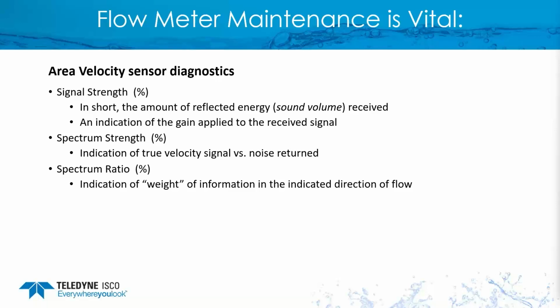Now the spectrum ratio is the indication of the weight of information of the direction of flow. Simply stated, it's just looking at what direction the flow is going. So this is the one place where you may see the spectrum at 100%, indicating that it sees 100% of the water coming directly at it. If there was some debris in front of the sensor, creating some swirling, that's when you're going to see the ratio start to go down.